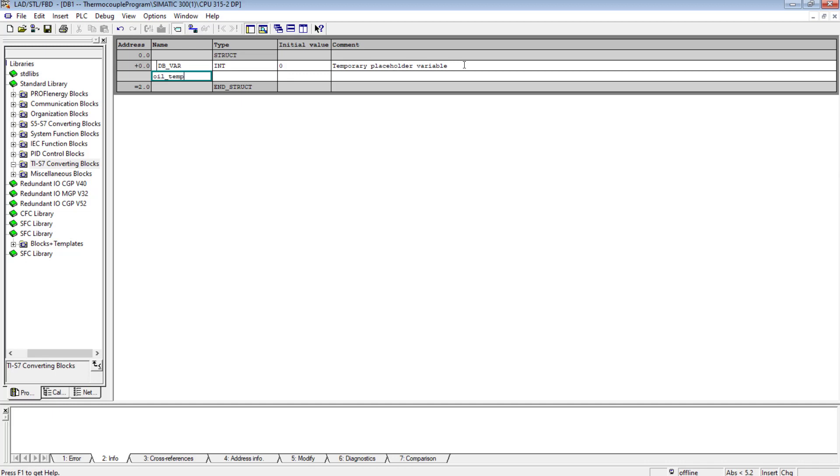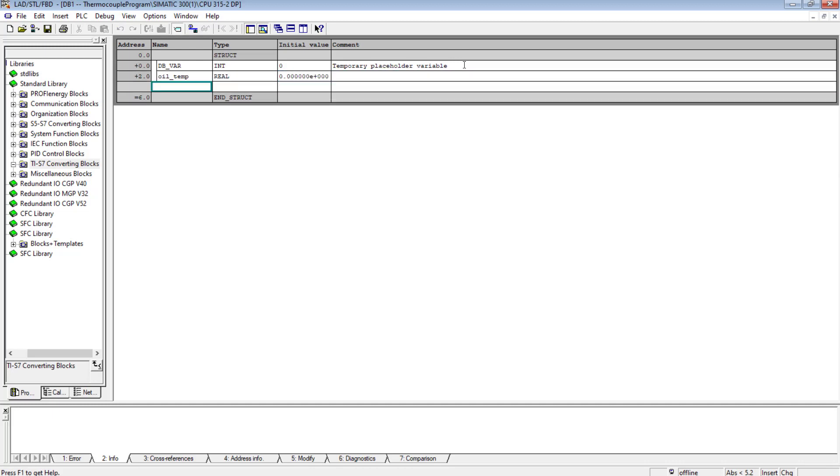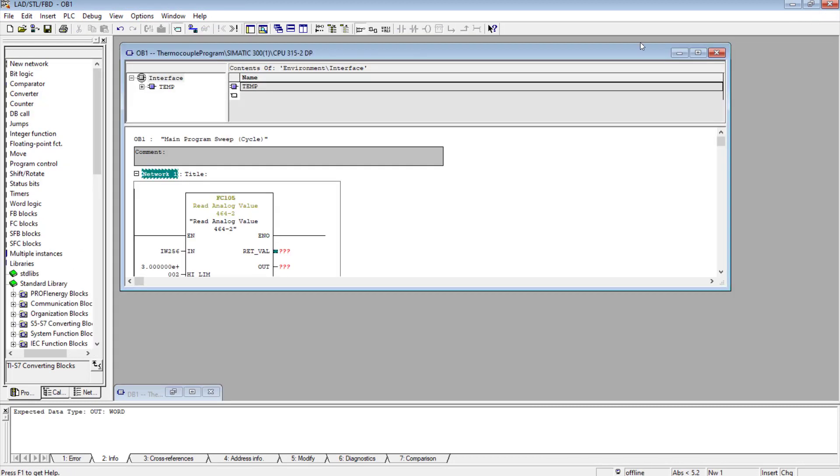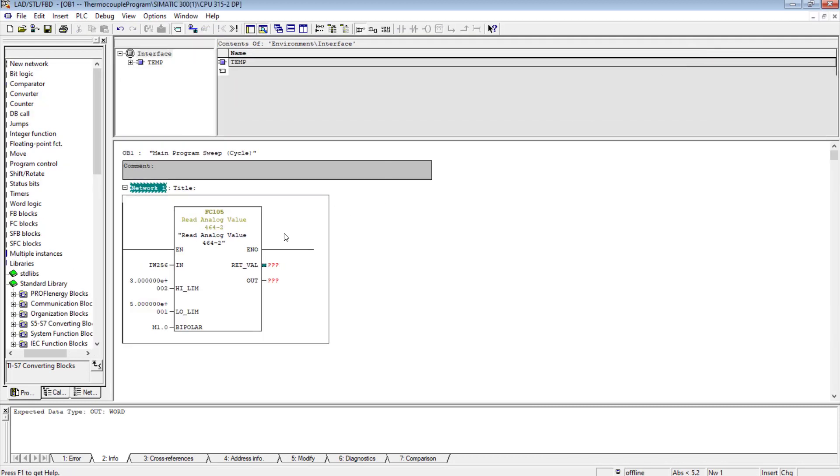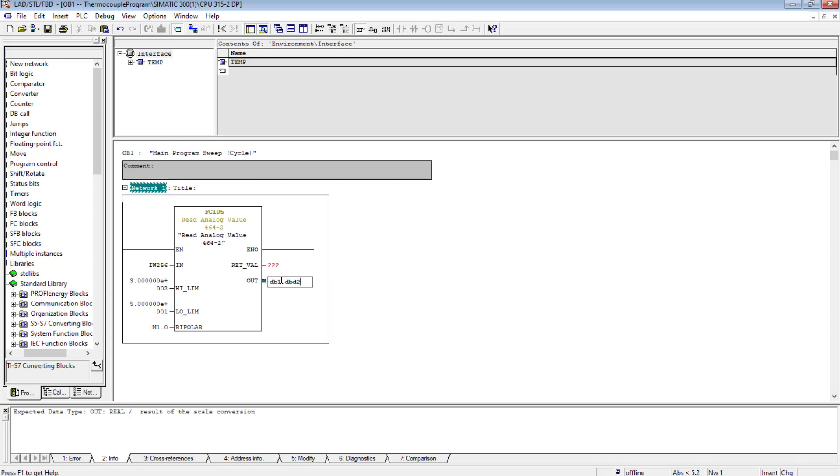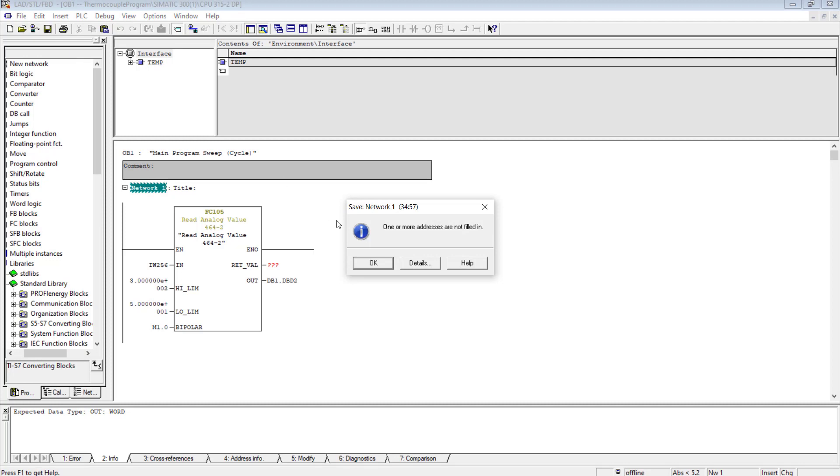Create data block DB1. This is the shared DB, that means it can be used anywhere in the program. Oil temperature 0.0. I will save it and I will try to access DB1.DBD2 in the OB1. The out value is the real value so I have interfaced DB1.DBD2 with this out.